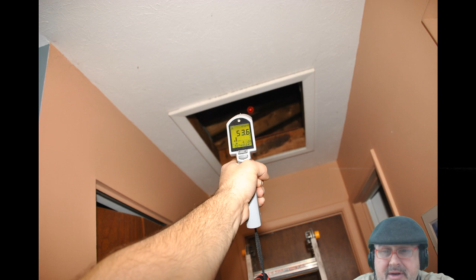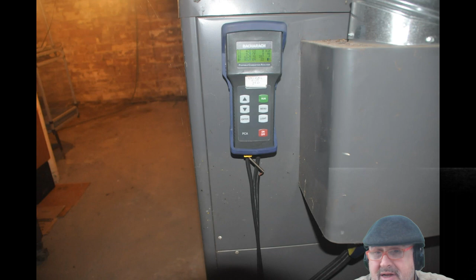Okay, what about carbon monoxide, incomplete combustion? These heating guys, they don't test your house. They come in there, oil your furnace, change your filter, charge you $200, tell you you need some high-low limit control or something, and you're out $500. And guess what? You're still getting sick. They didn't check for combustion analysis. Most of the time, you got to drill a hole in the flue. You want to check the combustion.